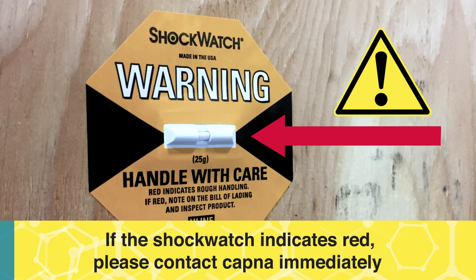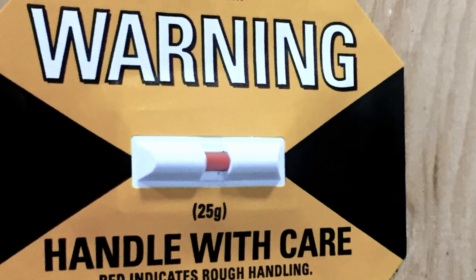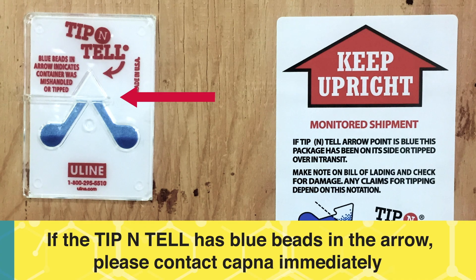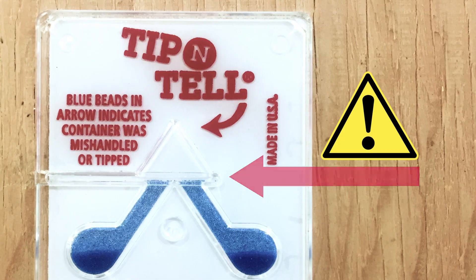As soon as you receive your crate, inspect the crate, check the ShockWatch and the Tip-N-Tell. If the ShockWatch indicates red, please contact Capna immediately. If the Tip-N-Tell has blue beads in the arrow, please contact Capna immediately.